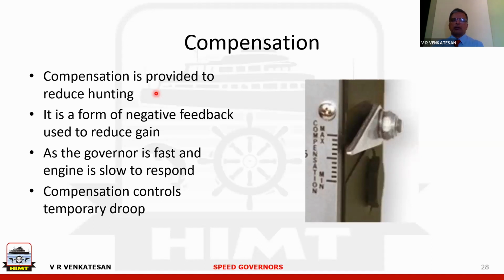Due to this, the governor will keep on increasing the fuel. And when the engine response starts, it will create an overshoot condition. The speed will go to the other side. So since the slowness of the engine cannot be compensated, what you need to do is bring down the speed of the governor, or make the governor respond a little more slowly. So it is used for reducing gain. This is the meaning, as the governor is fast and the engine is slow to respond.